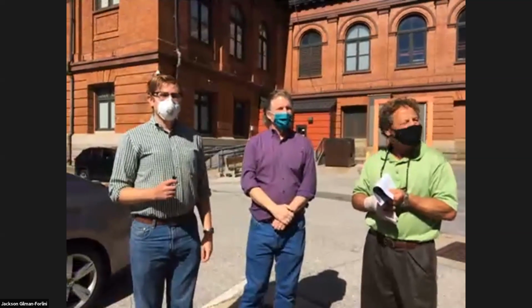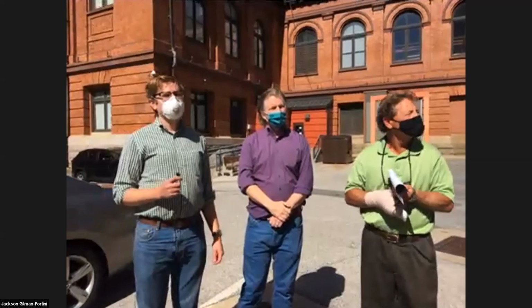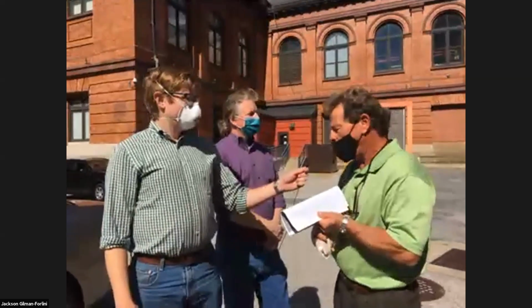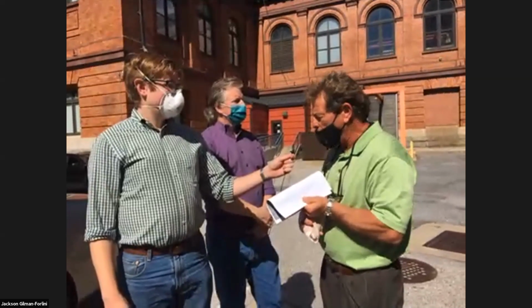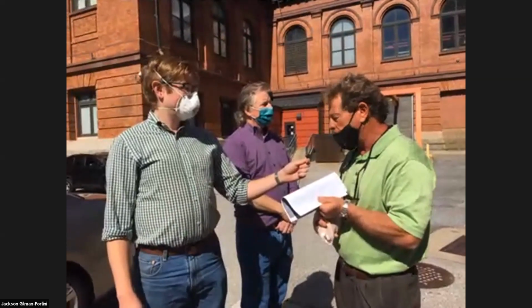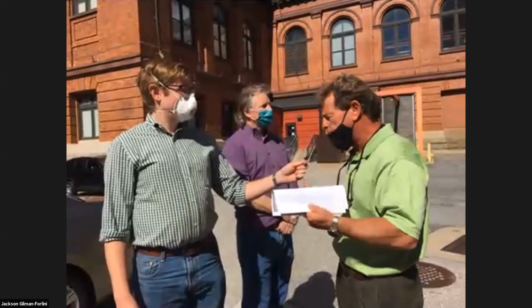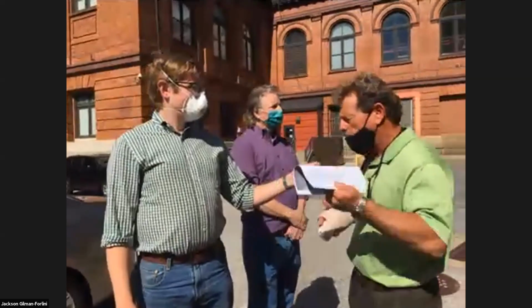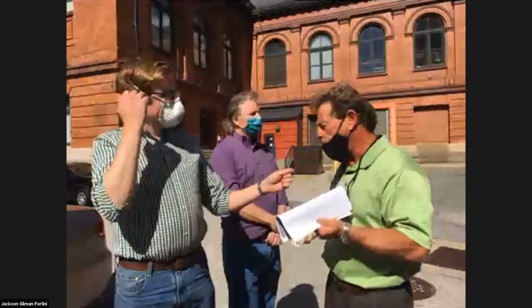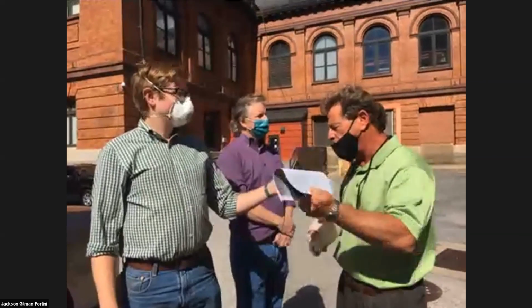Last question I have here is, where are the valves and how are they operated? The valves. All right, Chris, tell us more about the valves and how they're operated. Each pump has its own set of valves, and as the pump is called for, the pump will start and the valve will begin to open a few seconds before the motor is fired up to capacity. As the pump is motoring up, the valve is opening, thus allowing a smooth transition for the flow to be pulled up from the wet well out into the discharge side of the pump. So there are no suction valves here. We have what we call a vacuum system, which actually pulls the water up into the pump and then allows the discharge side to function electrically.